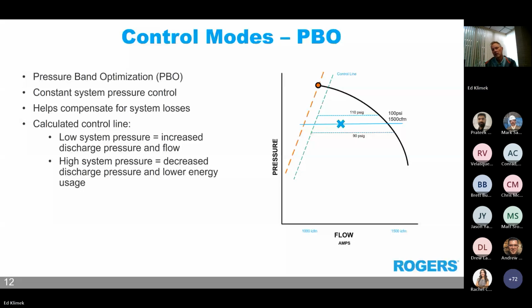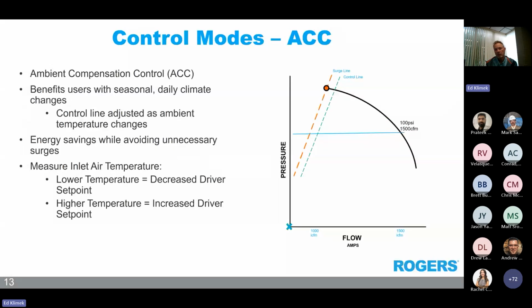And the next mode is considered ambient compensation control. It's really designed for customers that experience daily or seasonal temperature changes. ACC runs an algorithm that will automatically adjust the compressor control line by monitoring the inlet air temperature. The control line will adjust to ensure maximum turn down in lower inlet air temperature conditions, helping to ensure maximum energy efficiency. During higher air temperature conditions, the control line will adjust to a higher driver set point, ensuring the avoidance of unnecessary surge events.